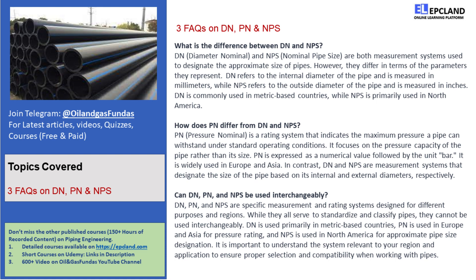On the other hand, DN and NPS are measurement systems that designate the size of the pipe based on its internal and external diameters, respectively. So, while DN and NPS give you information about the size of the pipe, PN tells you about its pressure capacity.